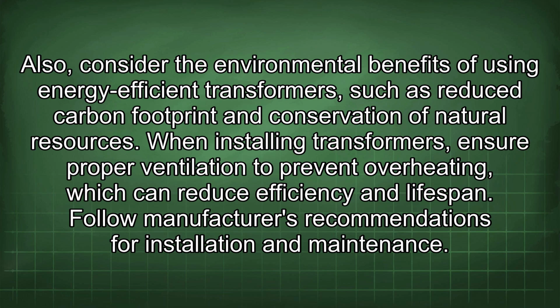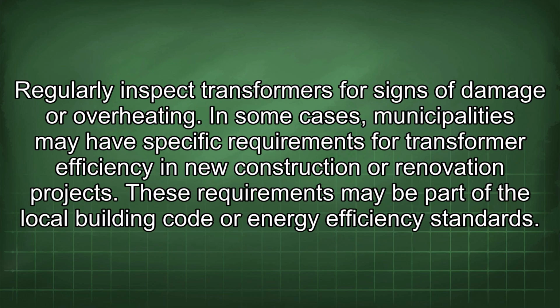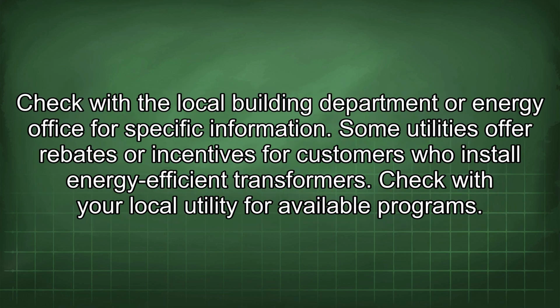When installing transformers, ensure proper ventilation to prevent overheating, which can reduce efficiency and lifespan. Follow manufacturers' recommendations for installation and maintenance. Regularly inspect transformers for signs of damage or overheating. In some cases, municipalities may have specific requirements for transformer efficiency in new construction or renovation projects. These requirements may be part of the local building code or energy efficiency standards. Check with the local building department or energy office for specific information. Some utilities offer rebates or incentives for customers who install energy-efficient transformers. Check with your local utility for available programs.